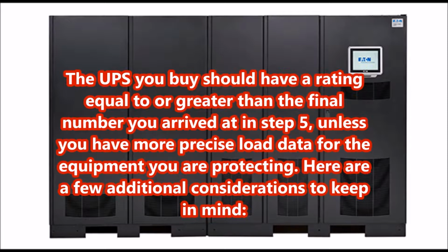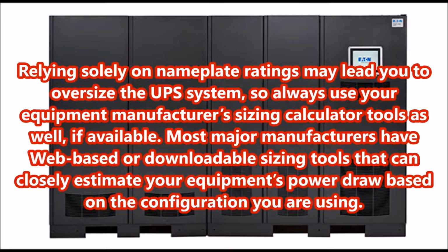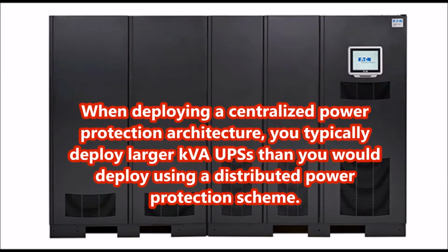Here are a few additional considerations to keep in mind. Relying solely on nameplate ratings may lead you to oversize the UPS system, so always use your equipment manufacturer's sizing calculator tools as well, if available. Most major manufacturers have web-based or downloadable sizing tools that can closely estimate your equipment's power draw based on the configuration you are using. When deploying a centralized power protection architecture, you typically deploy larger kVA UPSs than you would deploy using a distributed power protection scheme.